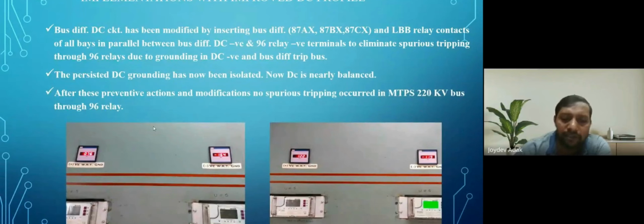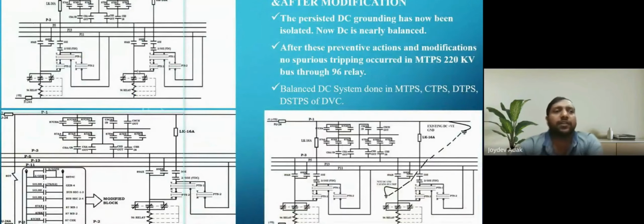After that, this is the bus differential scheme. You have to check only this part: this is the main bus portion and this is the condition. In the presently existing condition, if this is the circuit and this is the 96 relay, this is called the bus differential relay. If it operates, then after operation of this relay it will trip all other breakers on that bus, so that the system collapses and isolates the faulty part.